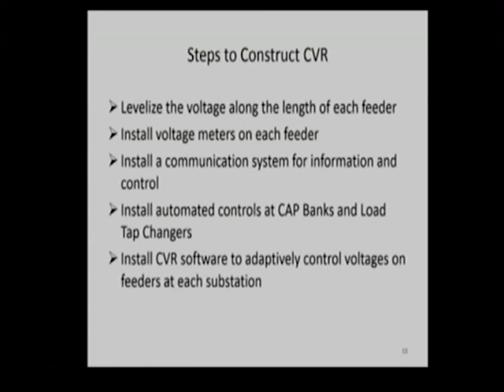Then we need to install voltage meters on each of the feeders. And that can either be in the form of meters out on the transformers or at various points on the feeders, or it could be with smart meters at the customer's location. Either one will work. We then need to install a communication system, if one doesn't exist, to get the data back to a central location so that we can do this monitoring and control. And then we need the software and control hardware that will make all of this work. And to install the CVR software to control the voltages on an ongoing, constant, continuous basis. So I'm going to walk through these one at a time and show some examples.